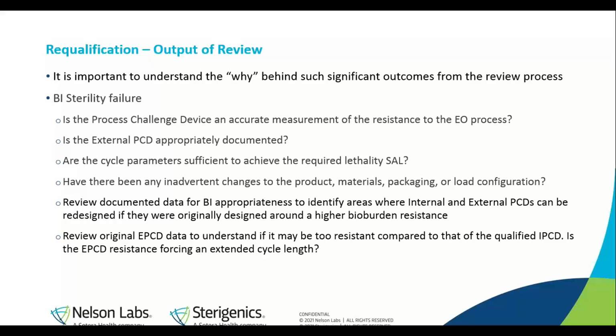Have there been any inadvertent changes to the product, materials, packaging, or load configuration? Sometimes those small changes can add up. What you would also want to do is review the documented data for BI appropriateness to identify areas where the internal and external PCDs can be redesigned if they were originally designed around a higher bioburden resistance. We'll get more into bioburden in the next slide. You want to review the original EPCD data to understand if it may be too resistant compared to that of the qualified internal PCD. Is the EPCD resistance forcing an extended cycle length?